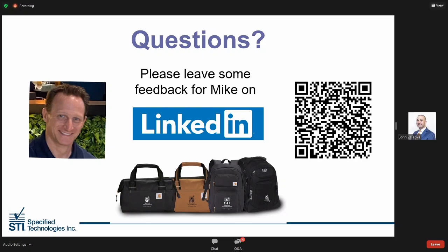All right. A question came in about Intertek static versus dynamic joints. UL, it's pretty easy. They have an S or a D. Is there anything in the Intertek system number, I guess, is the question, where it would say whether it's dynamic? Eric, you there? Yes, hi. Can you still hear me? Yeah. Normally it's in the system description. If you look at the system, it will reference movement as a description in the design. For example, if you look at our design 120-03 or 120-07, in the heading it will have a description for movement if the system is tested for that. UL, you're correct. UL lists the systems per movement, either CWS or CWD. And as you're going through your design work, just feel free to send us some information and we can guide you quickly into the right systems that you'll use, so you don't have to search through all the systems that we have.